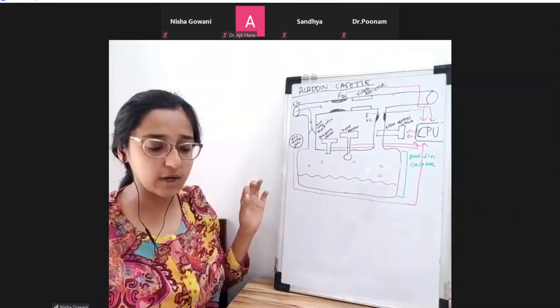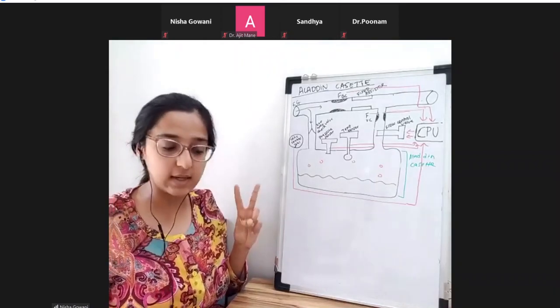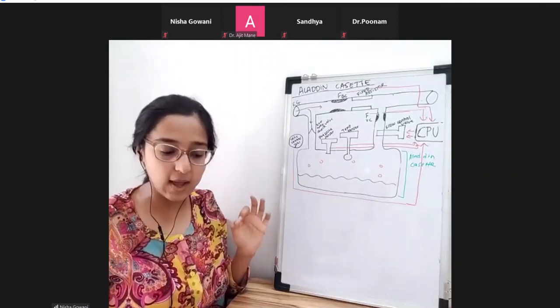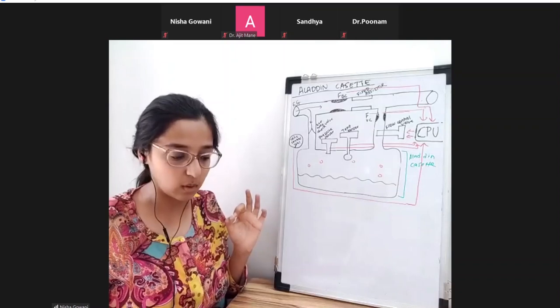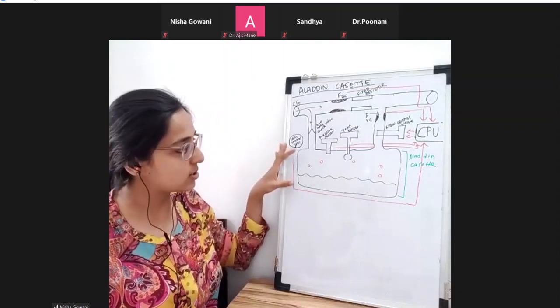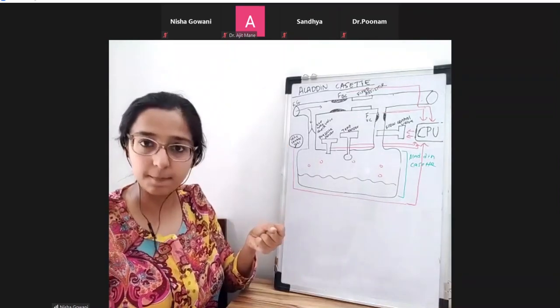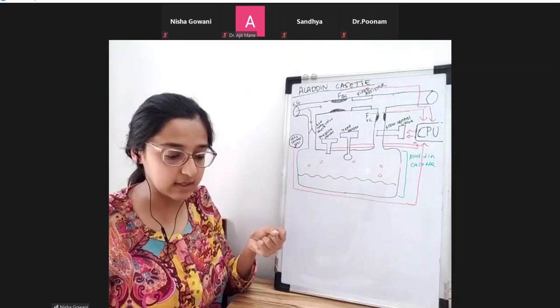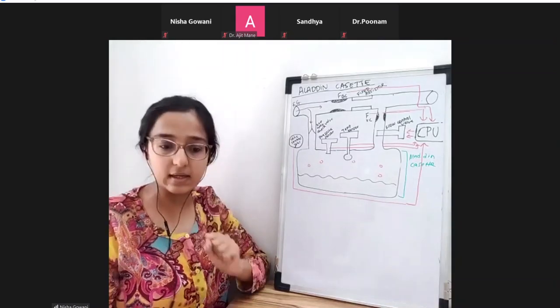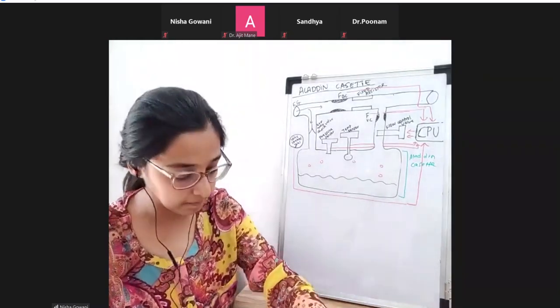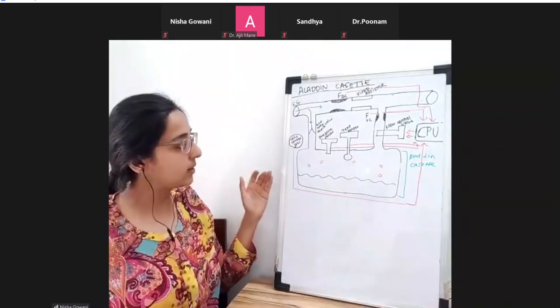Now, this is going to be found in two machines, the Datex-Ohmeda S5 ADU and the GE Aisys system. This agent-specific cassette is inserted into the anesthesia workstation. It is color coded and magnetically coded, as I told you previously. So now, what are the parts over here?